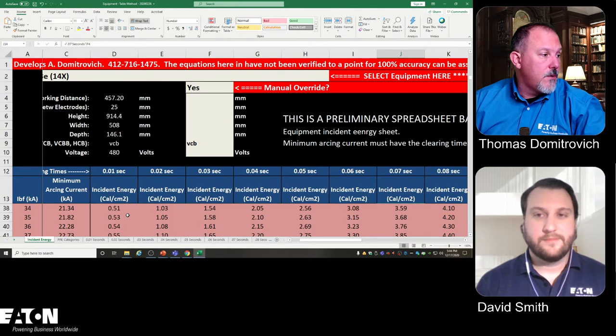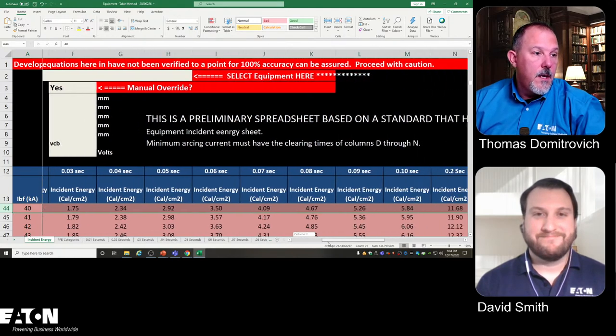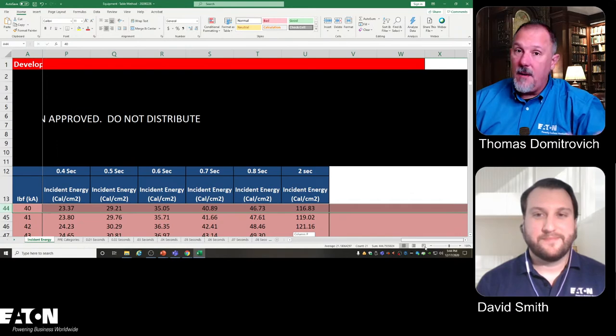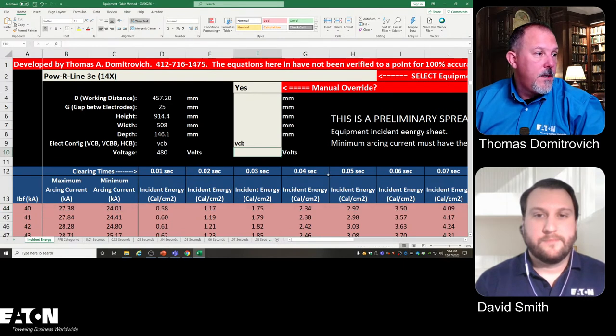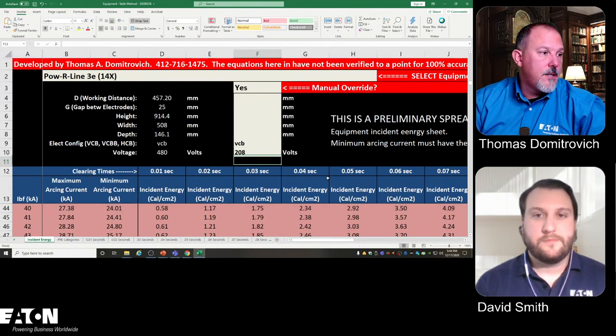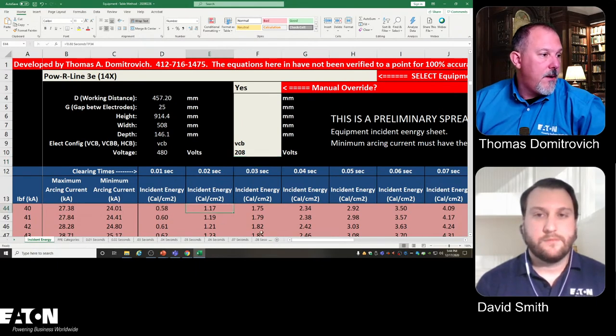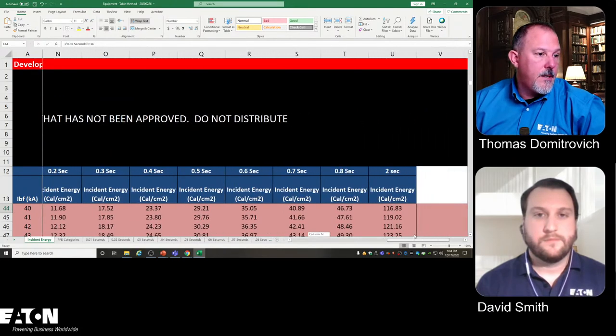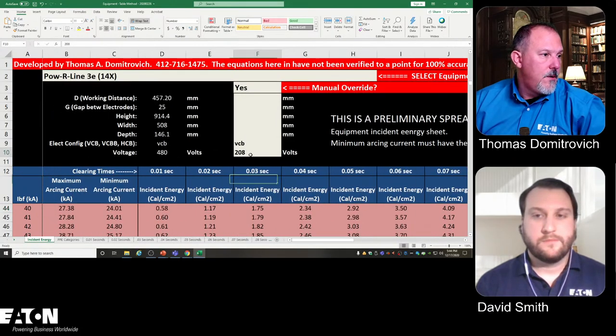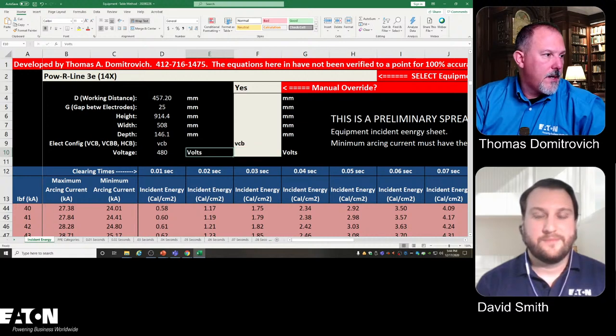Now, let's take the bolted fault current up to 40,000 amps, right? At 0.02 seconds of clearing time, I'm at 1.17 calories. At 2 second clearing times, I'm up over 100. All right, and that's at 480. Now let's change the voltage down to 208 for that same 40,000 bolted fault current value. I'm at 1.17, and I'm still at 116.83. So my voltage really, 480, my voltage isn't impacting that.